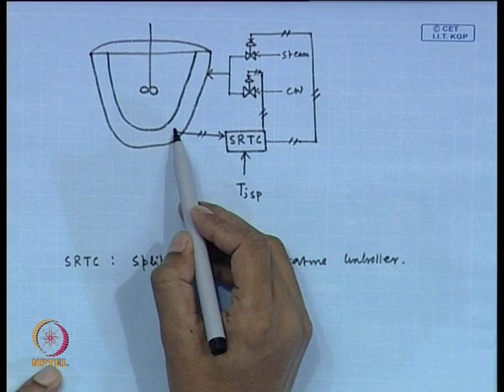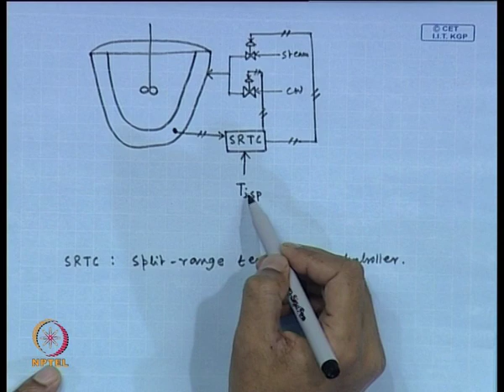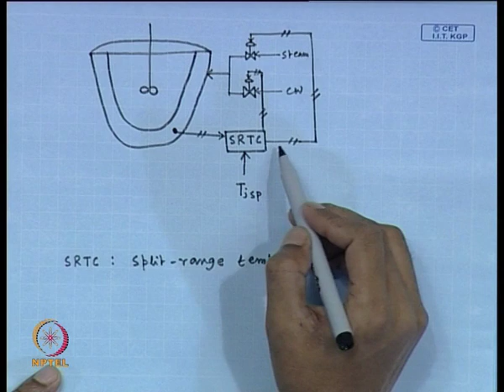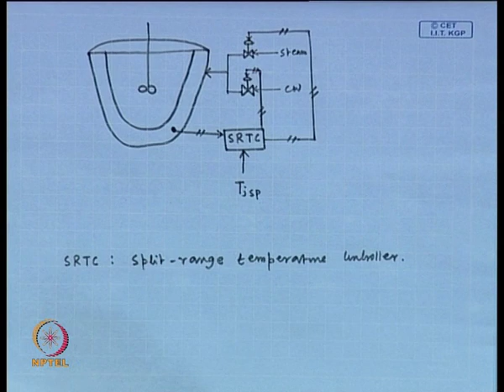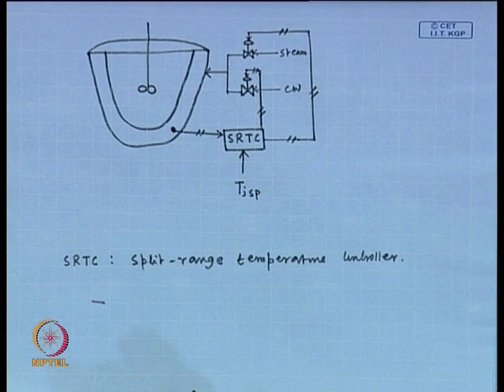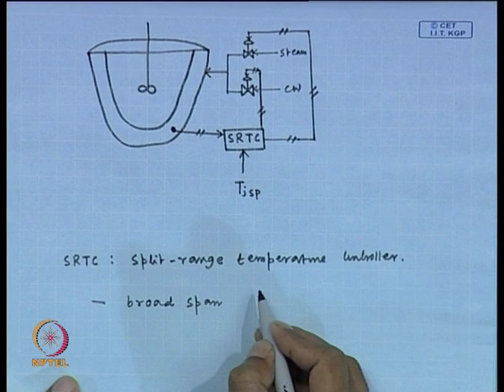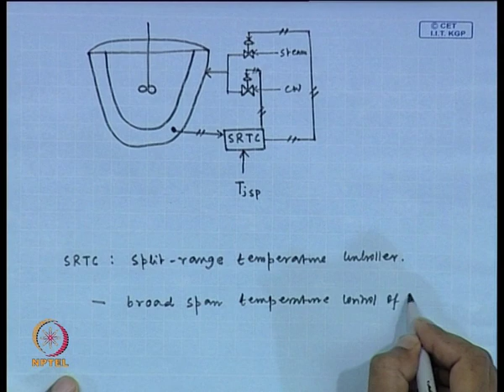This is the jacket temperature which is measured, and the set point of the jacket temperature is also supplied to this split range controller. Then this controller manipulates both steam as well as cooling water for maintaining the temperature throughout the batch operation, which varies from 15 to 100 degrees Celsius. Fine. So, this is the split range controller, and this controller is used for broad span temperature control of small plant or pilot scale plant.